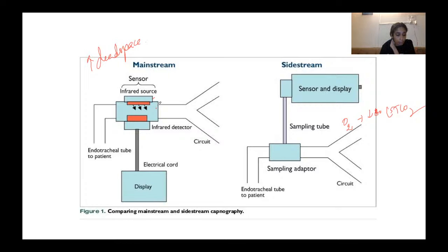Burns have been noted sometimes when they're doing face, head and neck surgeries. The endotracheal tube cannot be kept to this side; it has to be brought down along the length of the patient. So maybe at that point contact could have caused thermal burns. To prevent this, it is necessary to put a piece of aluminium foil between the skin and the analyzer.